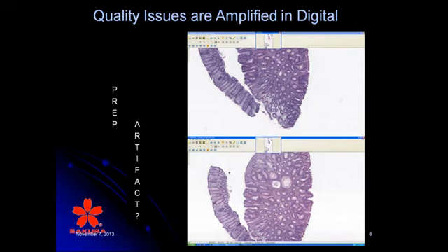So all of a sudden, you start taking into consideration what's going on with your tissue stain at a more intimate level. And what we found out was basically this is thick and thin. We had one slice, the wheel speed of our microtome versus the wheel speed of the next section that came through, which was quite amazing because we were thinking we had an issue with staining itself.